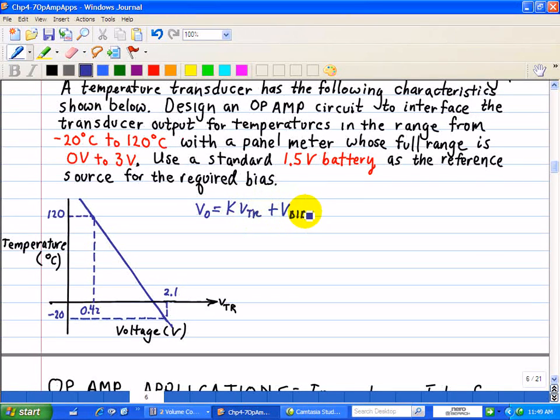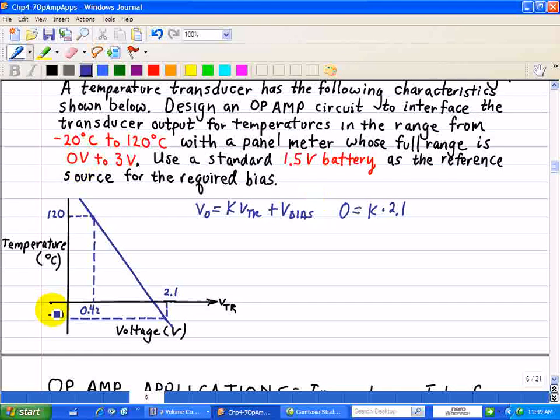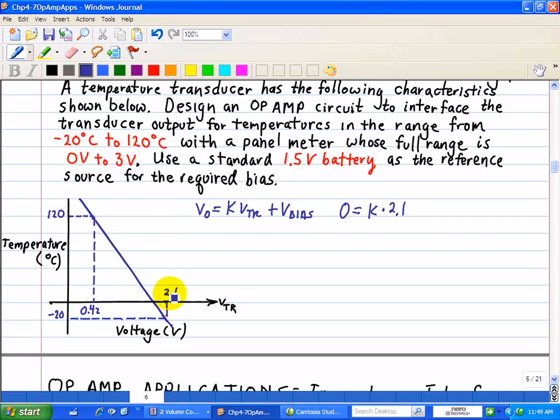I'm going to use this equation again to solve for our K and V bias. So in this example, 0 is equal to K times 2.1. So 2.1 times K corresponds to the 0 volt range. So negative 20, 2.1 to 0, plus a V bias. And this is at minus 20 degrees centigrade.